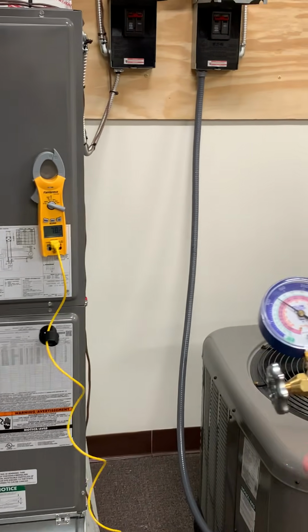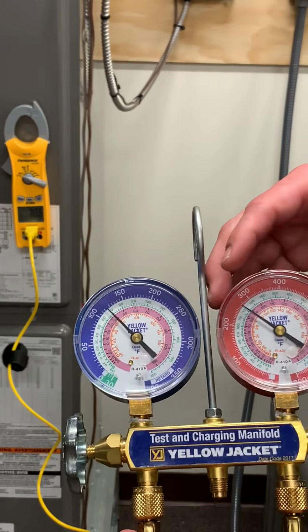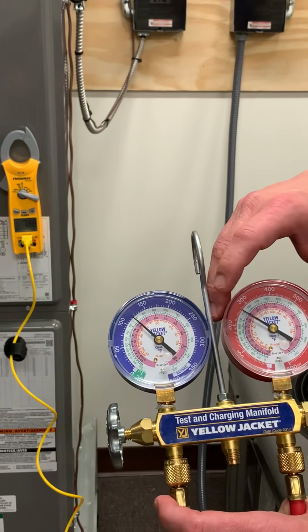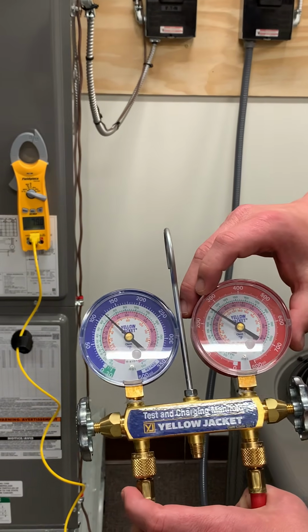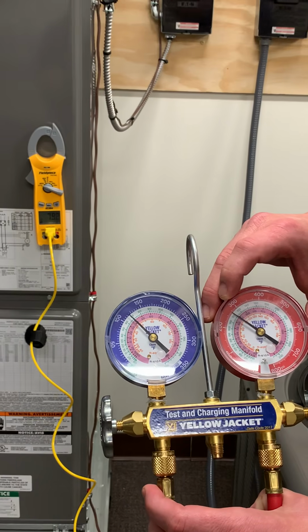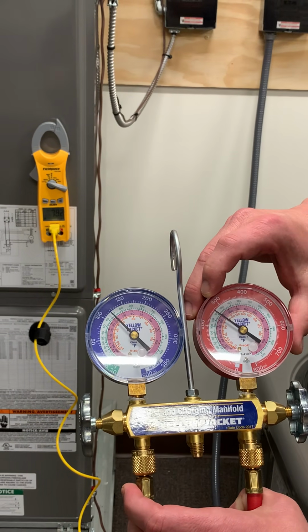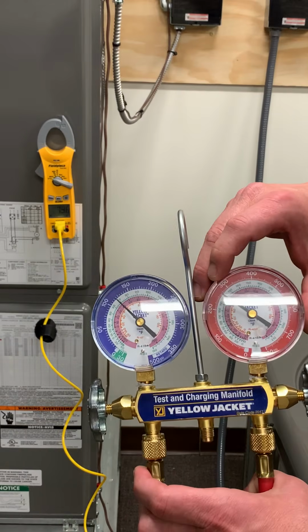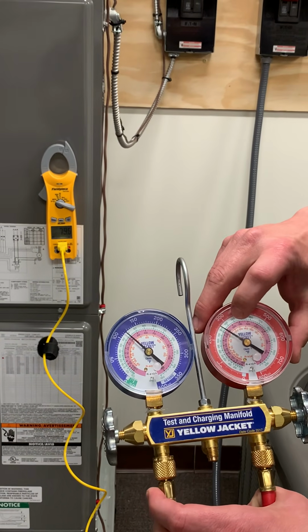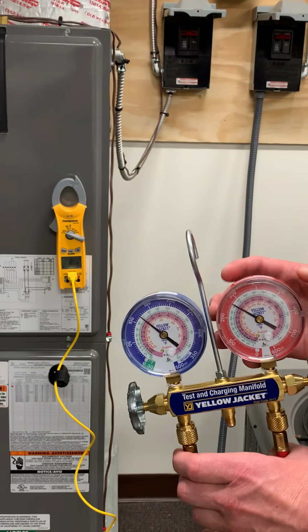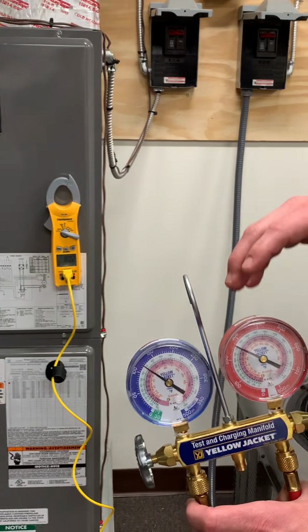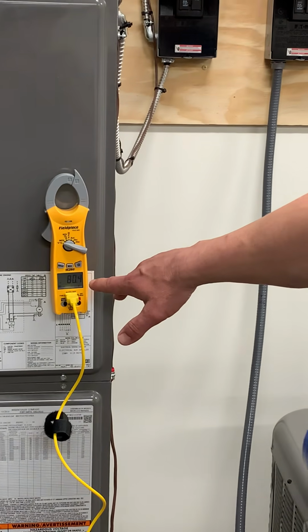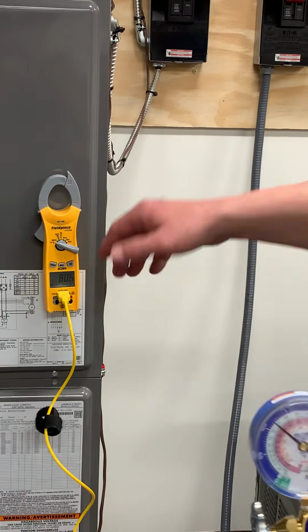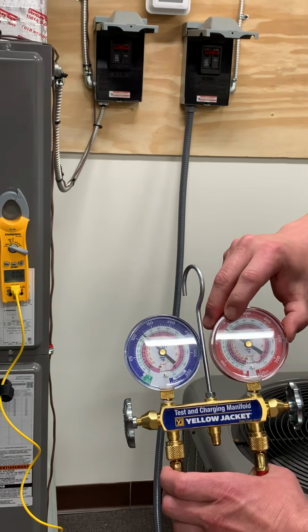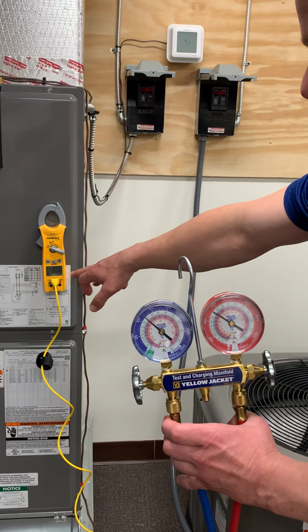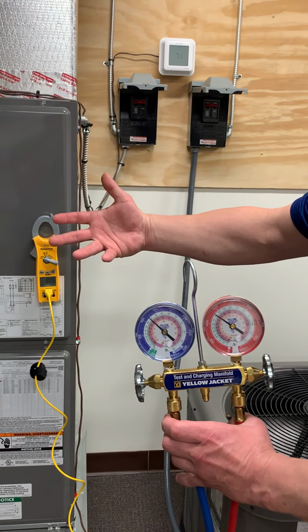The next thing I'm going to do is grab my gauge again, and this time I'm going to look at my high side pressure, and I'm going to do the same thing I did with superheat, which is convert my pressure to a saturation temperature. And you can see that I'm at about, it looks like, 265 PSI. And that converts to about 87 degrees saturation temperature. I take my actual line temperature, which seems to have settled out around 80 degrees, and I subtract that from my saturation temperature. So I have 87 minus 80, which lets me know I have 7 degrees of subcooling.